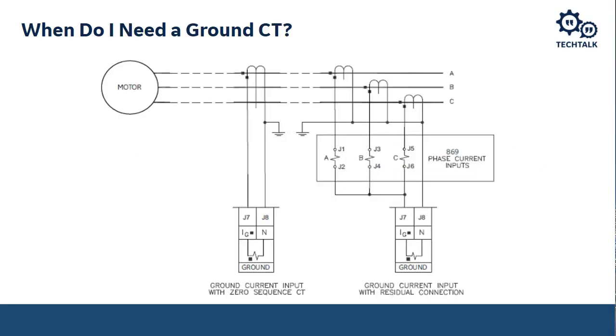And of course, we then use current to detect ground faults, and this is for low impedance and solidly grounded systems. This is pretty much what we use in most installations where we have motors, impedance grounded systems, and solidly grounded systems. There are two methods of measuring the ground fault current. One, to the right on this picture, is where we have the three-phase CTs connected into the relay, and they're residually connected to the ground input in the relay. This is referred to as the measured ground current, or the residual ground current. On a balanced power system, the A, B, and C phase currents, as with the voltages, add up to 0 on that residual connection. However, if you have a phase to ground fault, then you would have current flowing into that residual, or ground, connection.